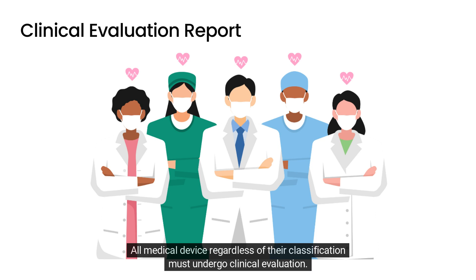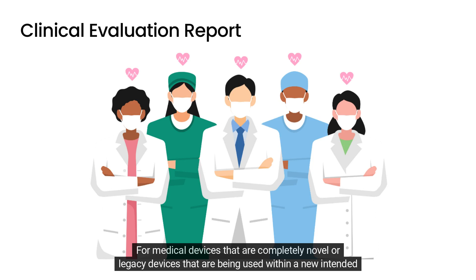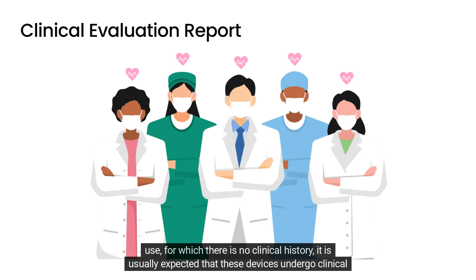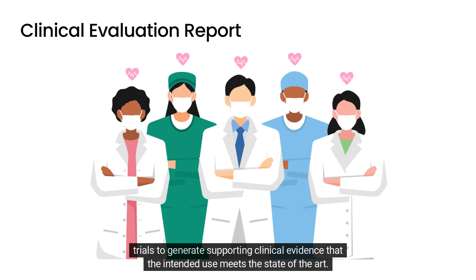All medical devices, regardless of their classification, must undergo clinical evaluation. For medical devices that are completely novel, or legacy devices that are being used within a new intended use for which there is no clinical history, it is usually expected that these devices undergo clinical trials to generate supporting clinical evidence that the intended use meets the state of the art.